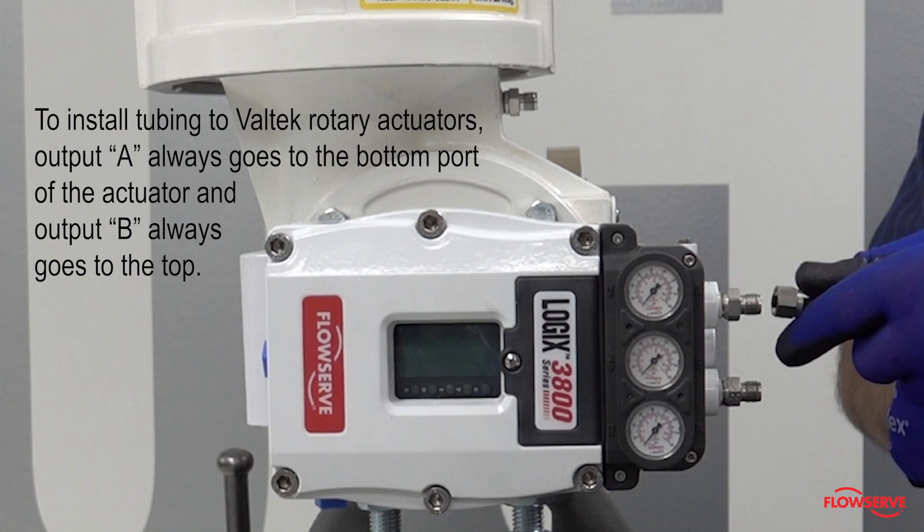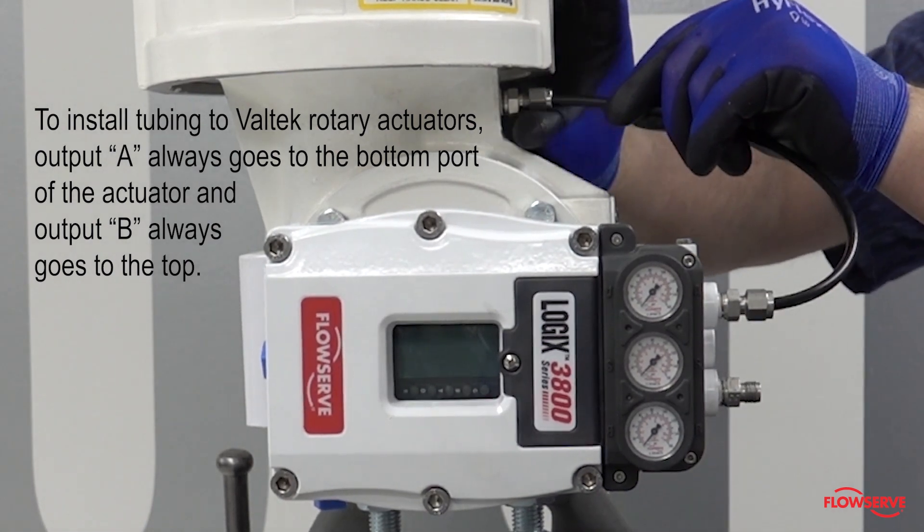To install tubing to Valtek rotary actuators, output A always goes to the bottom port of the actuator, and output B always goes to the top.